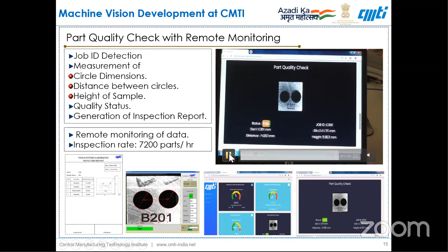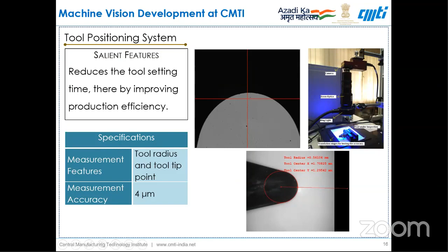This is another tool positioning system which we have developed. It is used for tool setting operation in one of the machines, an ultra precision turning machine developed by CMTI. This has been integrated. It measures the tool radius and the tool tip point to an accuracy of about 3 to 4 microns. It improves production efficiency because the tool setting time comes down. This is another system which we have supplied to one of our customers, running successfully at a production line.